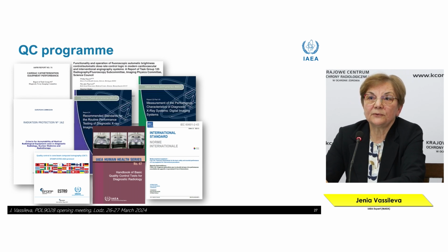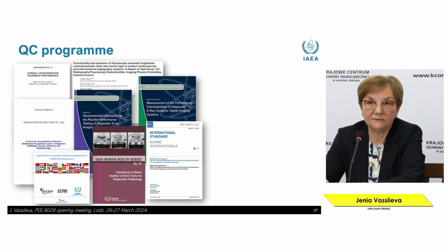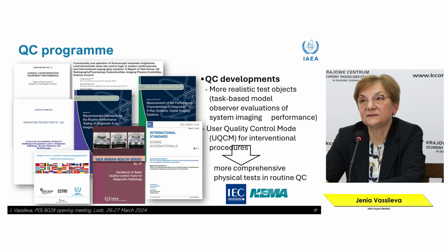So for a QC program in this field, there are many guidance documents. IAEA is also finalizing a new publication on QC in interventional radiology, but they are also published for QC development with different test objects, task-based models, observer evaluation of system performance, and the QC mode that I mentioned for interventional procedures that will provide opportunities for more comprehensive physical testing, the routine quality control.